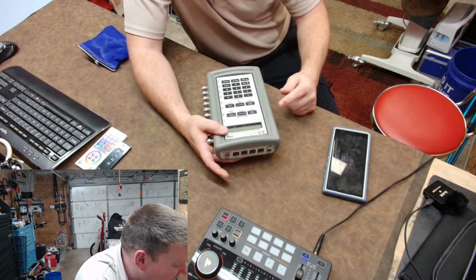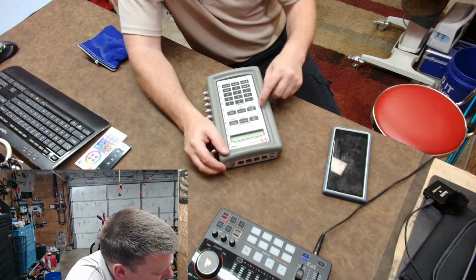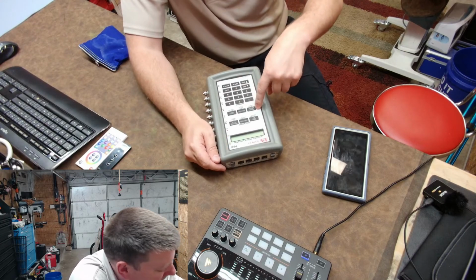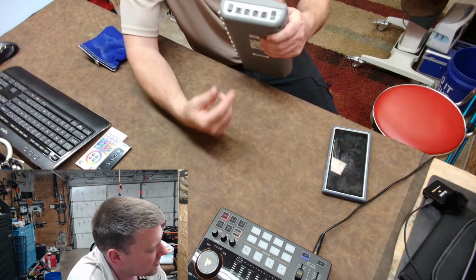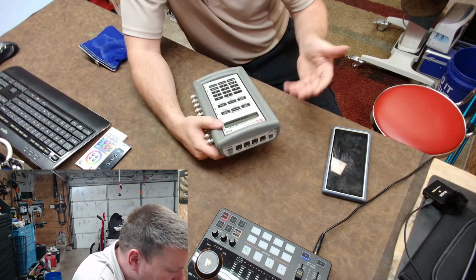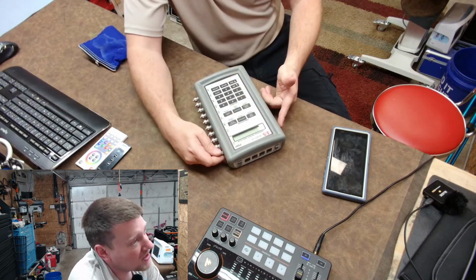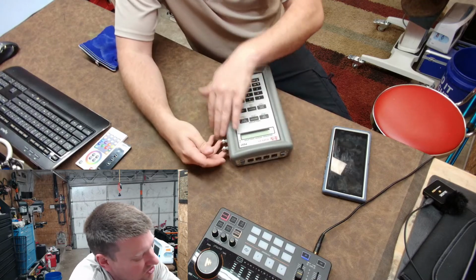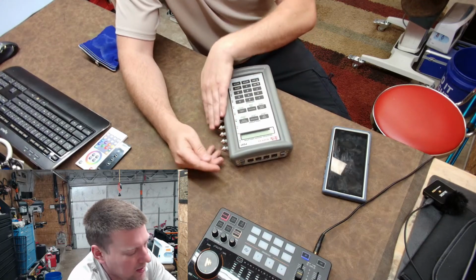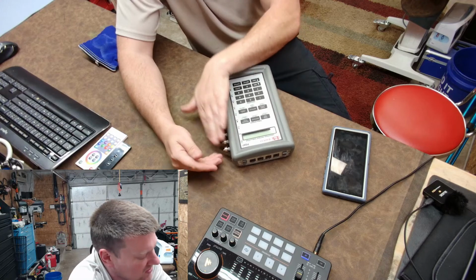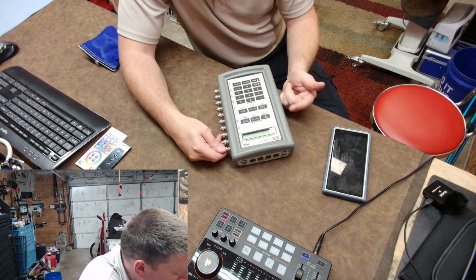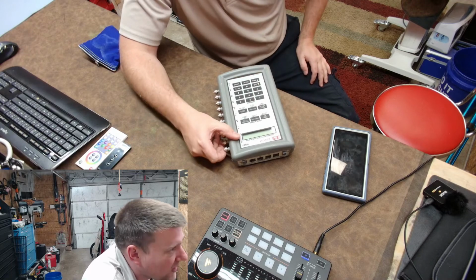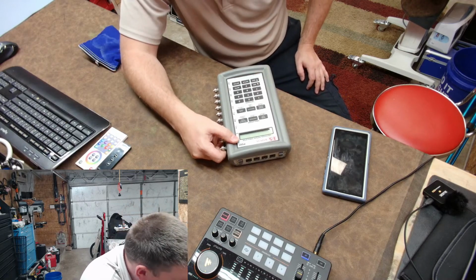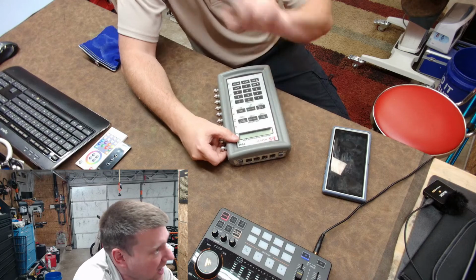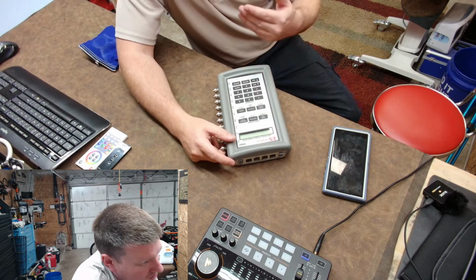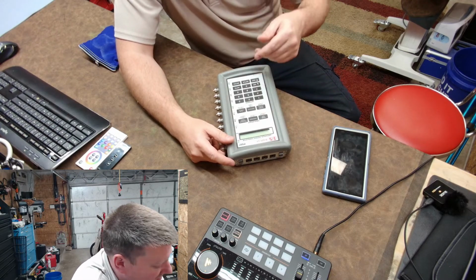The button down here is invasive blood pressure. So I can choose the invasive wave, and I can select the channel because remember there are 2 channels. And I can set the respiration. So respiration, it's checking your respiration rate using impedance over here on your ECGs. And I can set the RPM, that's not revolutions per minute, that is respirations per minute. I can set the ohms and the apnea. Apnea is when, you know, it senses that everything's at an all stop.